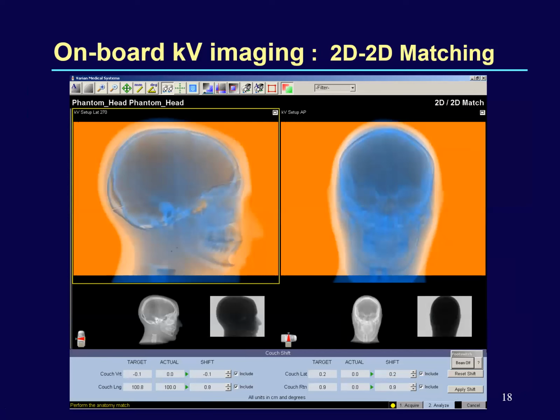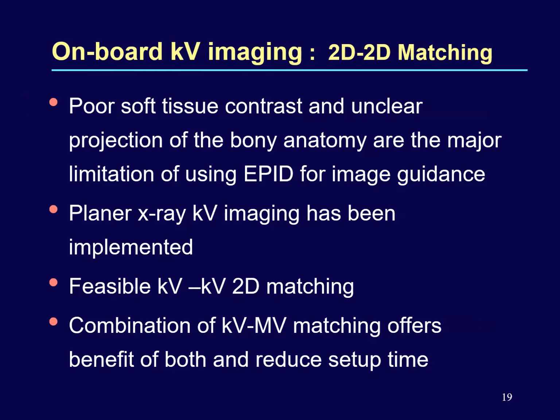For the onboard imaging system, one can have an AP and a lateral image and do a shift manually or automatically based on the bony structures, and one can evaluate the translational and rotational shift here. But remember, the roll cannot be evaluated nor corrected. The onboard imager offers the MV one, which EPID offered, with a very poor tissue contrast and unclear projection of the bony anatomy, and that was a major limitation of the EPID MV image. Hence, planar kV imaging has been very well accepted for good quality image guidance, because what we could see clearly, that is what we could match, reproduce and treat.